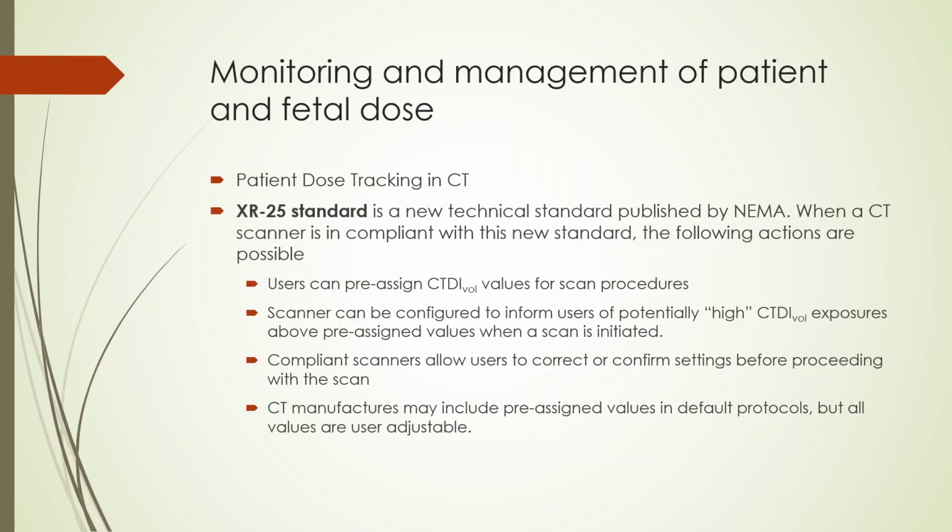Because CT is the largest source of medical exposure, we give it special attention here. A new US technical standard, XR25, was published by the National Electrical Manufacturers Association, or NEMA. CT scanners in compliance with this standard can be configured to inform users when scan settings will result in CTDI or DLP that exceeds pre-assigned values. Compliant scanners allow users, before proceeding with scanning, to confirm or correct settings that might lead to high exposures. Manufacturers may include pre-assigned values in default protocols, but all values can be adjusted by the user.